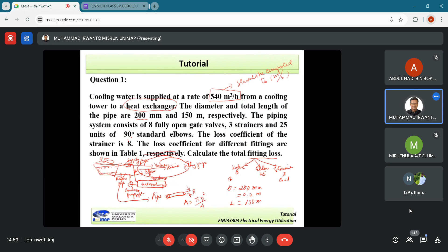Next we calculate the loss for the strainer. The number of strainers is 3, and the coefficient of the strainer is given from the question as 8. So we multiply 8 by rho, the water density 1000, and velocity 4.77 power 2, divided by 2. We obtain 273.8 kPa for the strainer.